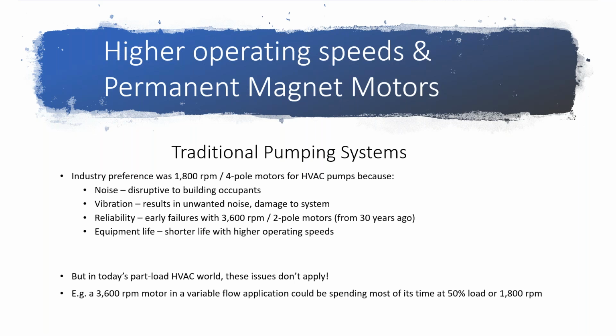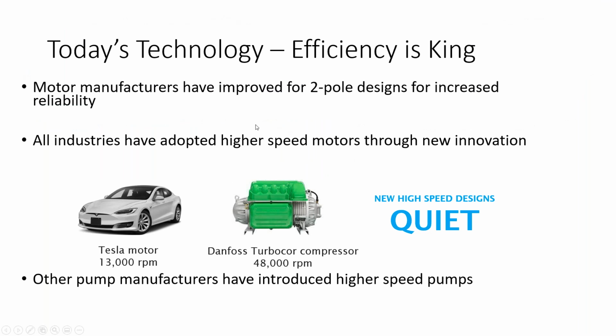But today we have a part load, so a lot of times you're running that 1800 RPM pump at about 300 to 700 RPMs, and your power curve is way off the map as far as how much power is going into that motor to put out a relatively low output. So for an example, a 3600 RPM motor in a variable flow application could be spending most of its time at part load or 1800. So now today's technology, it's not just what we're dealing with.